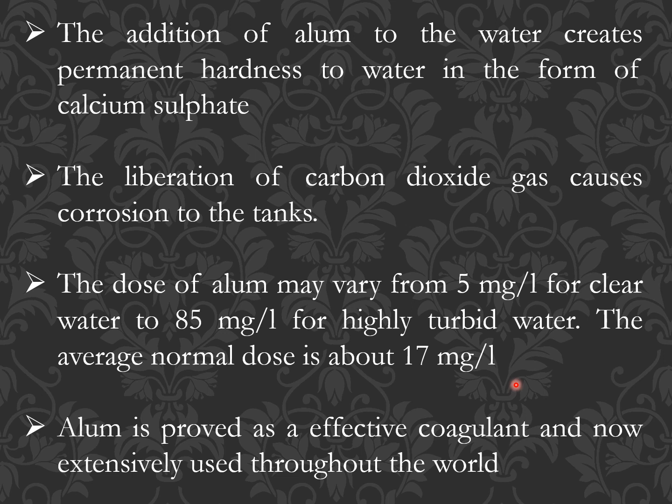They take the water and supply various amounts of alum to each jar. Actually 6 jars will be there, and in each jar they increase the dosage of alum by 2 ml, 4 ml, 6 ml, 8 ml, and so on.